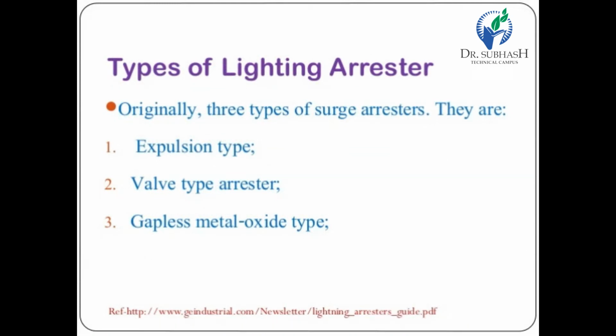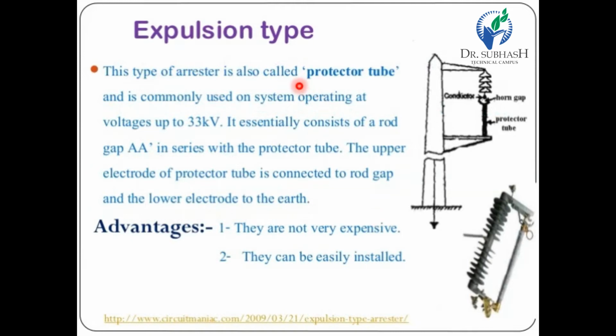Types of lightning arrestor. There are three types of lightning arrestors. The first one is the expulsion type, the second one is the valve type arrestor, and then the gapless metal oxide type arrestor. Now, what is an expulsion type lightning arrestor? This type of arrestor is also called a protector tube and is commonly used on systems operating at voltages up to 33 kV. It essentially consists of a rod gap in series with the protector tube.